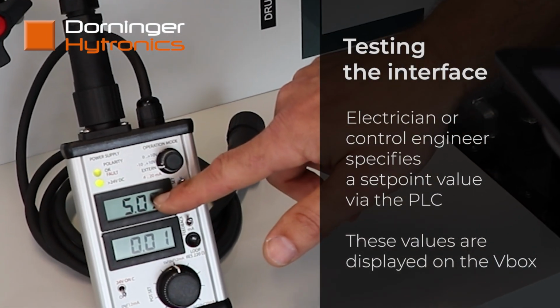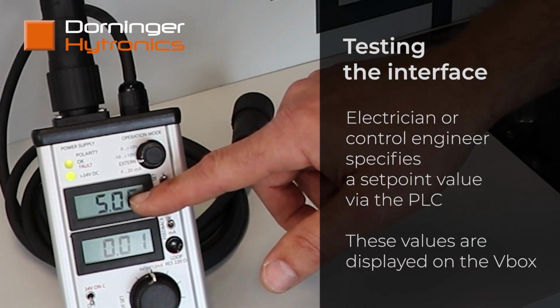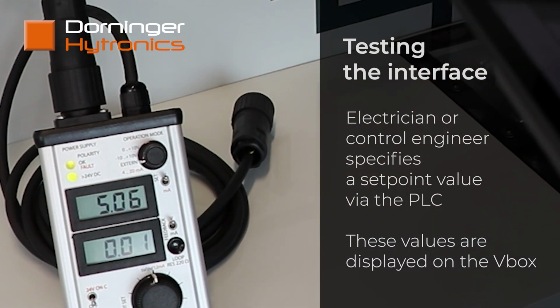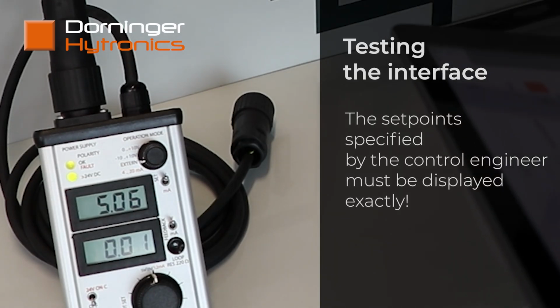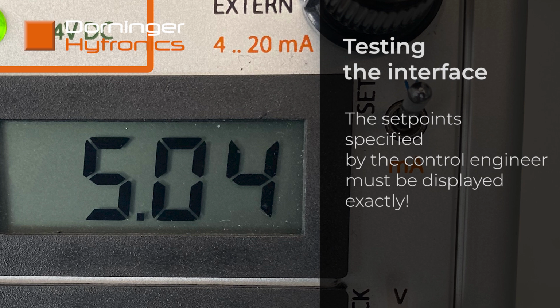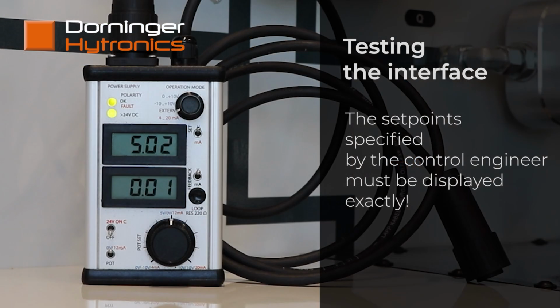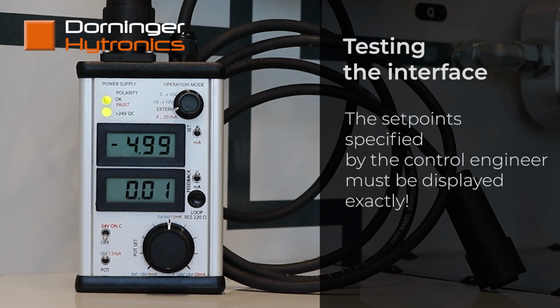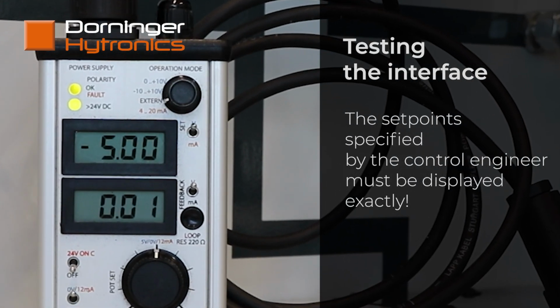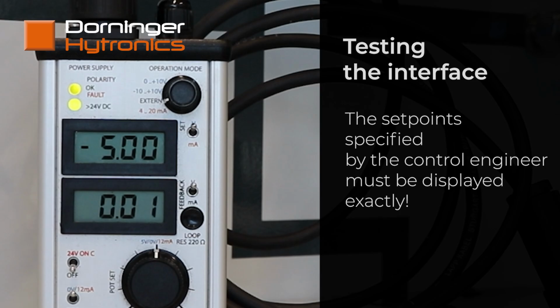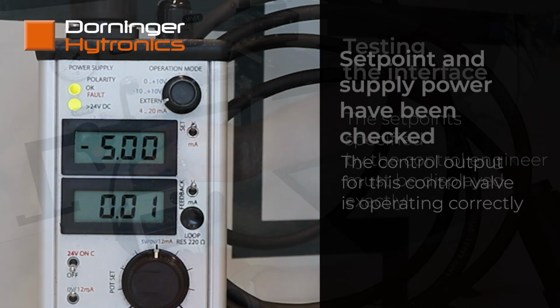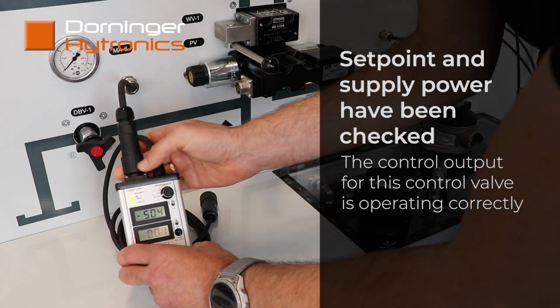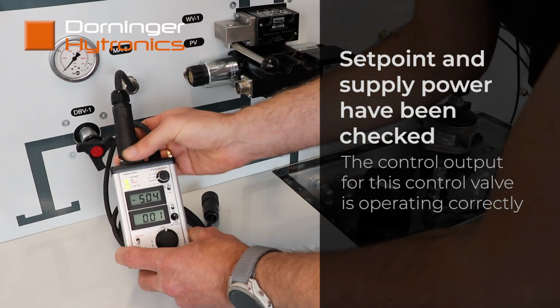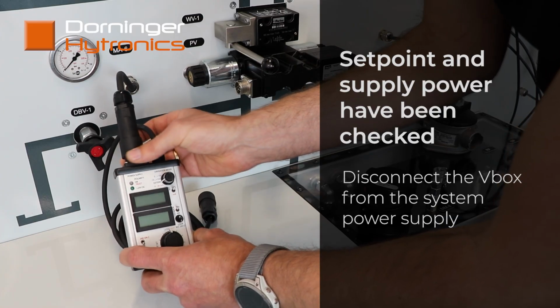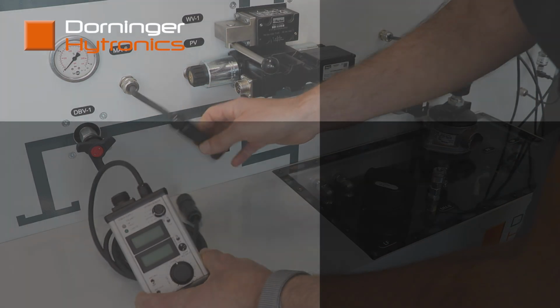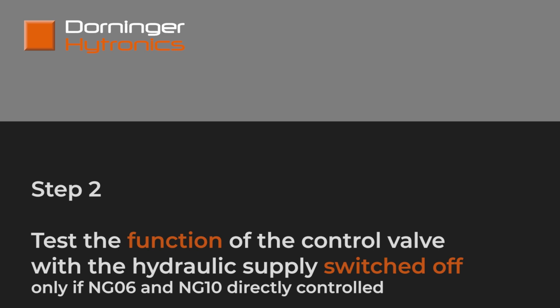In the next step, we check the interface between the control system and the control valve. To do this, the control engineer specifies a setpoint value via the PLC. This setpoint value is measured and displayed by the Vbox. In our example, a signal of plus 5 volts is output first, followed by a signal of minus 5 volts. If the setpoint value is displayed correctly on the Vbox, this means the control output for this control valve is operating correctly. The wiring for the setpoint signal and the supply voltage has therefore been checked. Please refer to our operating manual for instructions on how to check the feedback signal wiring. We now test the function of the control valve with the hydraulic supply switched off.